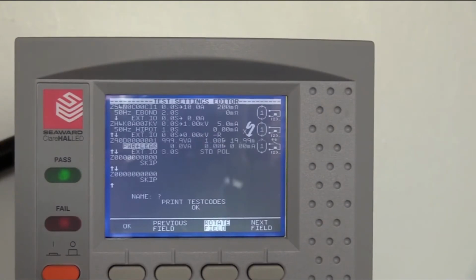Now this does 2 tests in one hit. So not only can we perform a power test and make sure that the power is where we would expect it to be, but also we can perform what's known as an earth leakage test. That earth leakage test defines any current flow, any stray current flow in the earth cable whilst the unit's in operation. Effectively, this is a kind of supplementary test to the Hipot test. In theory, if we have Hipot leakage, we would have earth leakage and vice versa.